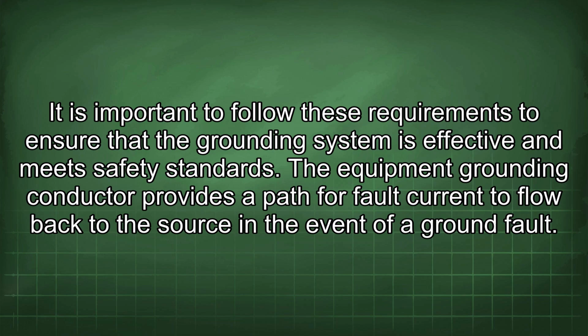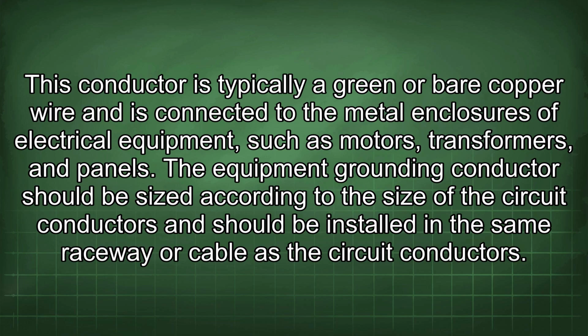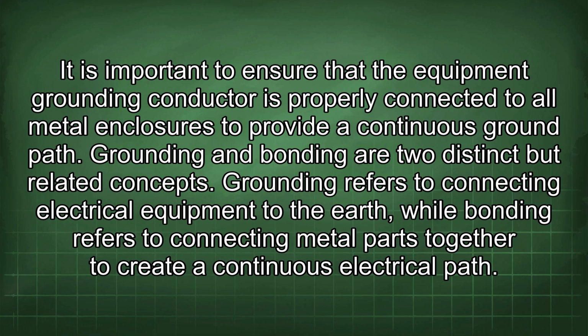The equipment grounding conductor provides a path for fault current to flow back to the source in the event of a ground fault. This conductor is typically a green or bare copper wire and is connected to the metal enclosures of electrical equipment such as motors, transformers, and panels. The equipment grounding conductor should be sized according to the size of the circuit conductors and should be installed in the same raceway or cable as the circuit conductors. It is important to ensure that the equipment grounding conductor is properly connected to all metal enclosures to provide a continuous ground path.